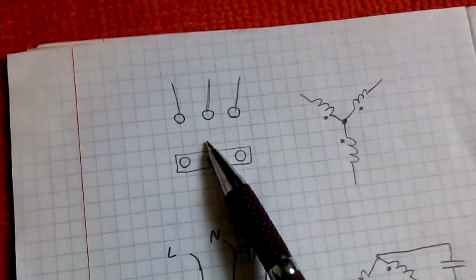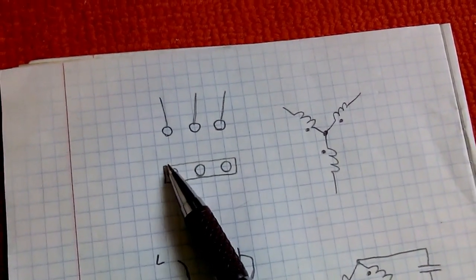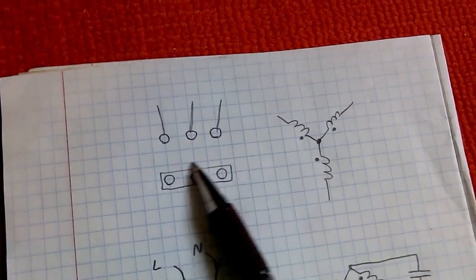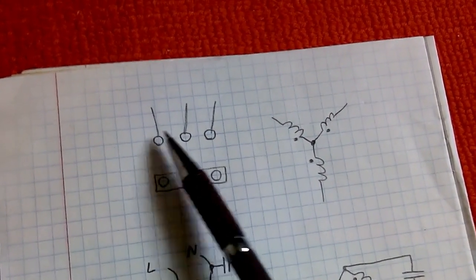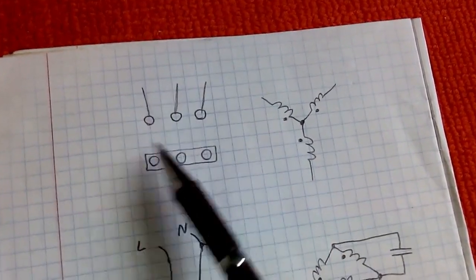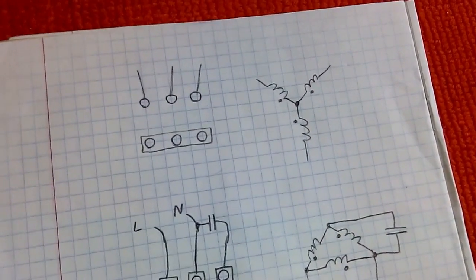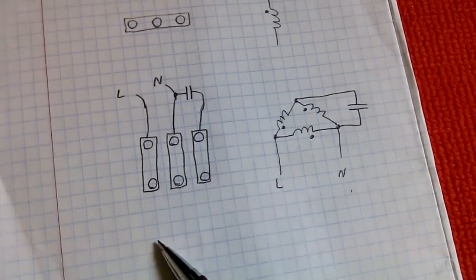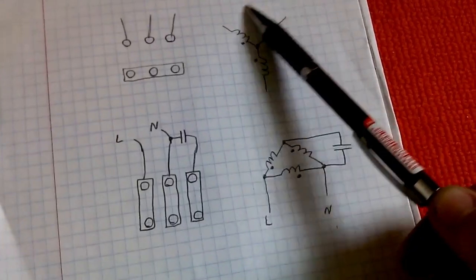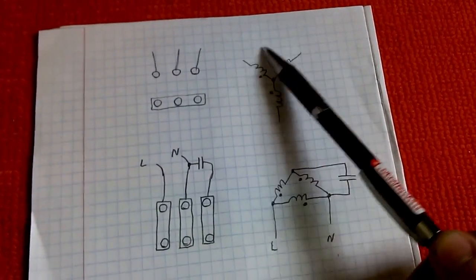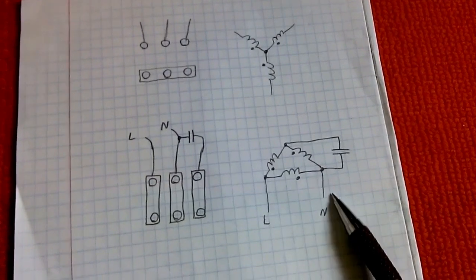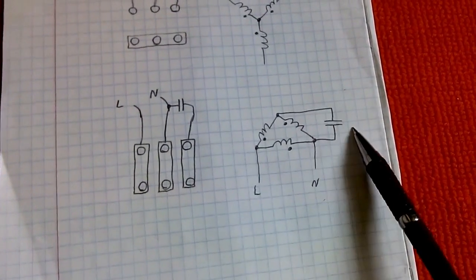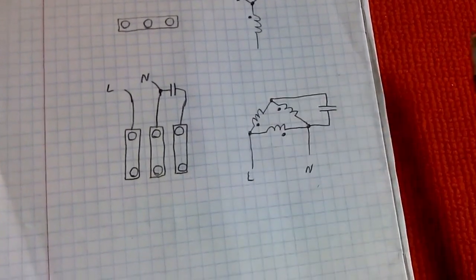Originally the setup looked like this: there was a bar shorting these together, and these were used to feed your three phases in. Now, to be used from a single-phase supply, you need to rewire the windings from a star configuration to a delta or triangle, and you will need a capacitor. That's necessary.